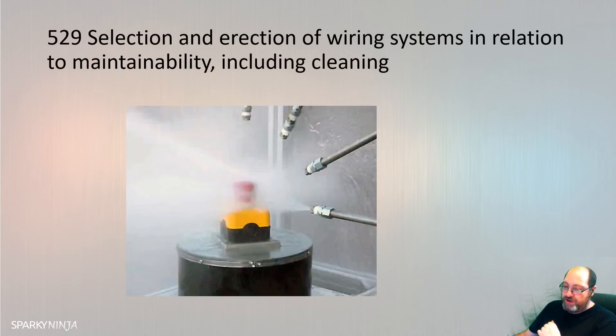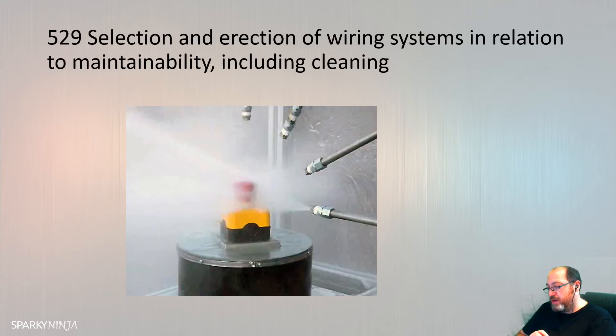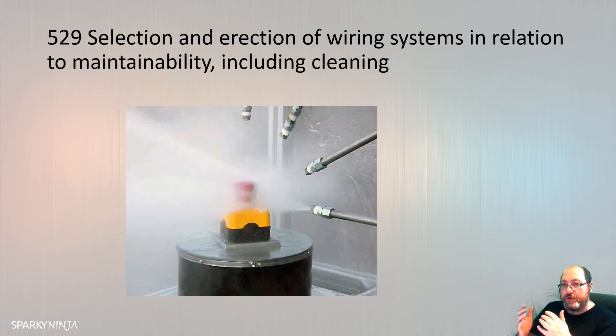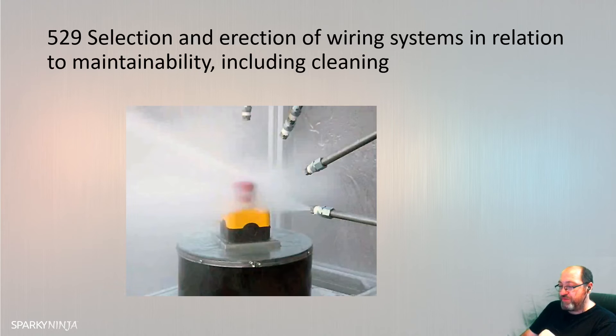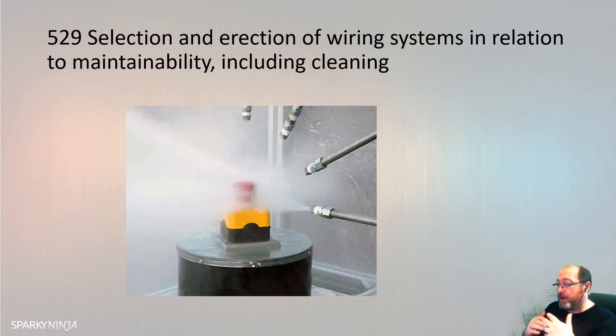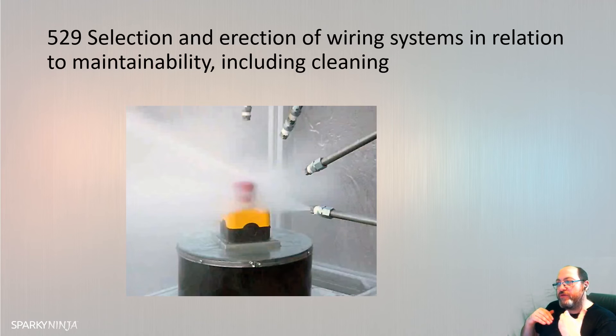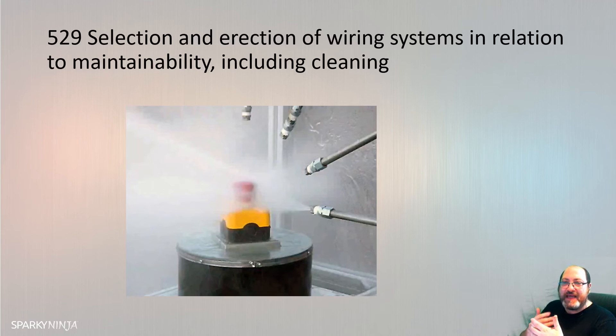To finish off chapter 52, we have selection and erection of wiring systems in relation to maintainability, including cleaning. With regards to maintainability, reference is made to 132.12 from Part 1: where it's necessary to remove any protective measure in order to carry out maintenance, provision shall be made so the protective measure can be reinstated without reduction of the degree of protection originally intended. Take for example a barrier or enclosure — if maintaining or cleaning equipment requires removing a lid or box, it shouldn't be damaged or weakened, and when reinstated it will be in no lesser a state.